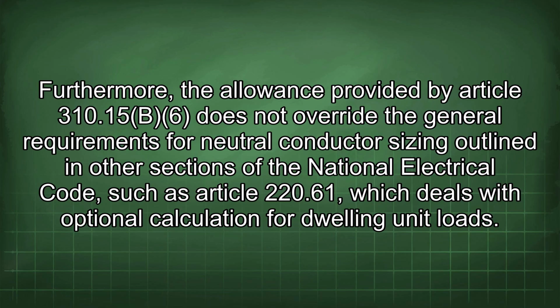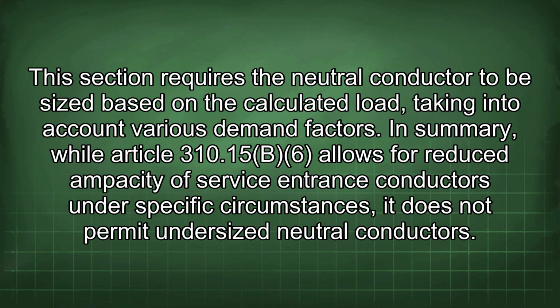Furthermore, the allowance provided by Article 310.15(B)(6) does not override the general requirements for neutral conductor sizing outlined in other sections of the National Electrical Code, such as Article 220.61, which deals with optional calculation for dwelling unit loads. This section requires the neutral conductor to be sized based on the calculated load, taking into account various demand factors.